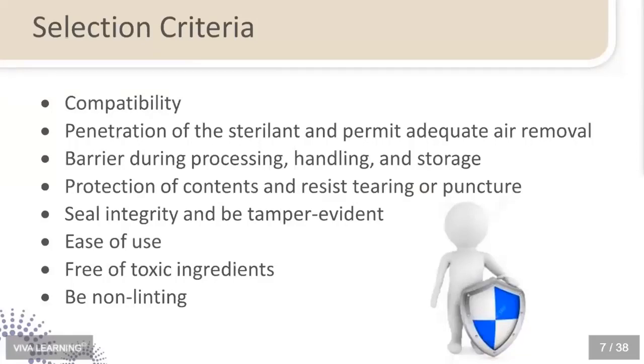You also have to look at if there's an adhesive tab, say to seal the sterilization pouch, or you're looking at steam sterilization adhesive tape. You want to make sure that it's going to be able to permit secure and complete closure. How wide is that adhesive seal on your sterilization pouch? Another thing they talk about is seal integrity and tamper evidence. If somebody mistakenly opens a pouch or a pack and says, oh, that's not what I needed, we have to be able to see that it's evident that the seal has been tampered with, and once it's open, it needs to be reprocessed, even if those instruments have not been used, because when you open it, it is no longer sterile.